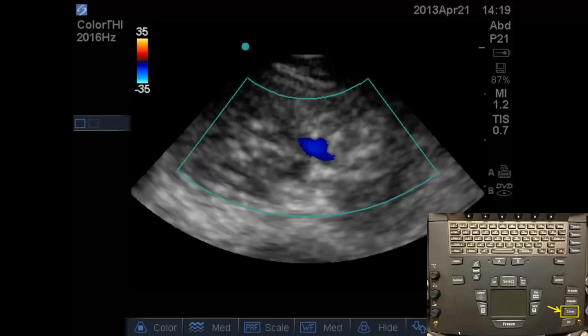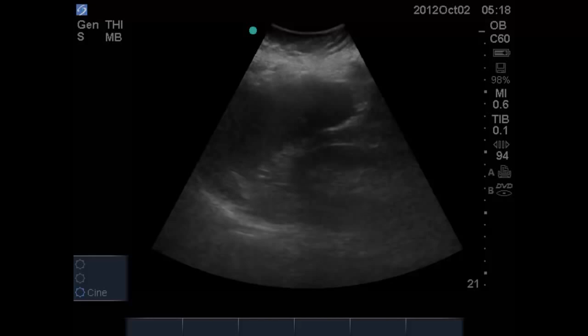Now that we have a high-quality image, we can use some of the tools to gather more information. The freeze tool can be used to hold a still shot of the current image on the screen. With the image frozen, you can scroll through frames in the queue using the overall gain knob. You can also scroll through these images by scanning left or right on the trackpad or by using the left and right arrow keys. Also, with the image still on the screen, you can use the generic caliper tool to measure objects on the frozen image.